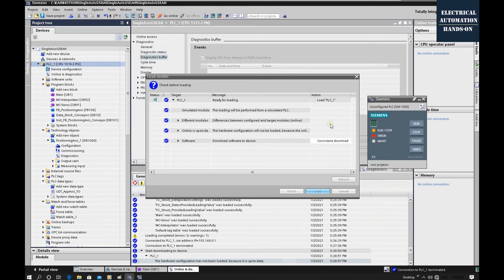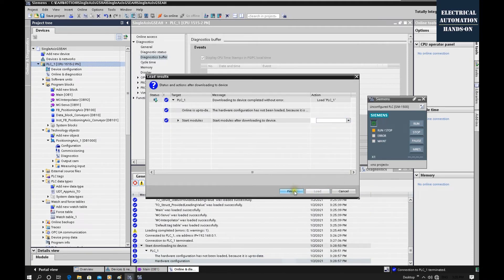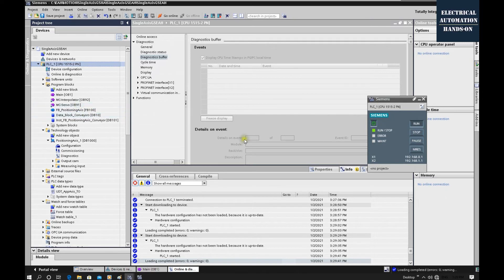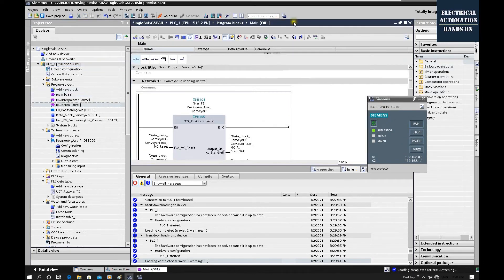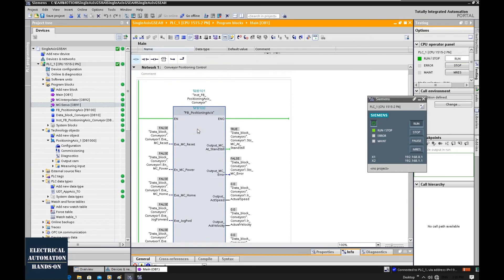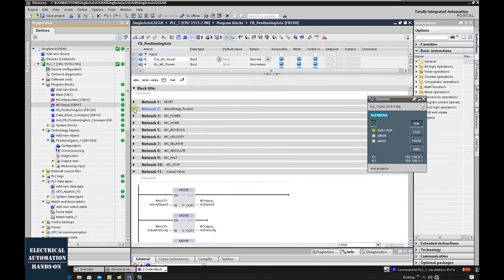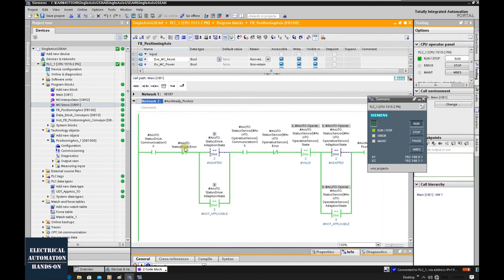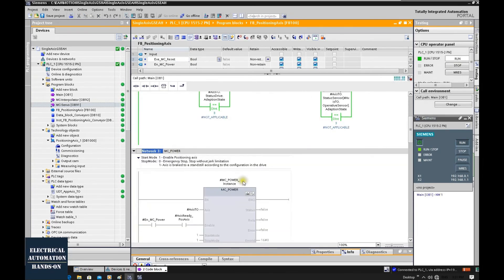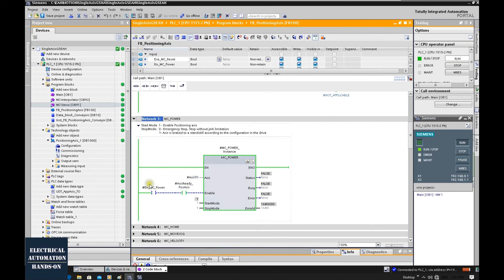Download, then restart the module. As we can see, once I increase the time, the simulator can start without any problem. If we hit Monitor On, the system shows stand-still status with no error arrow. Let's double-click to jump into the function block. Look at the axis ready signal — it's now showing ready — and to power on the axis: the axis is ready and waiting for us to power it on.